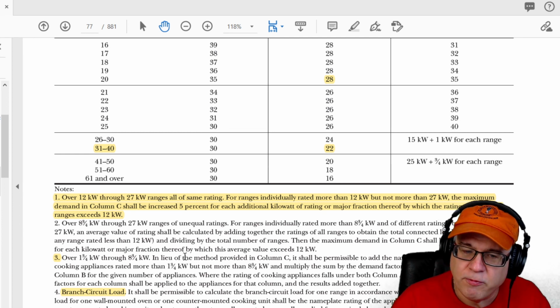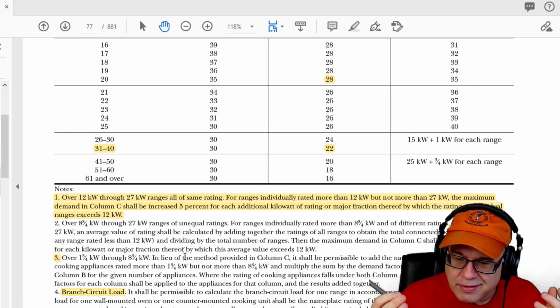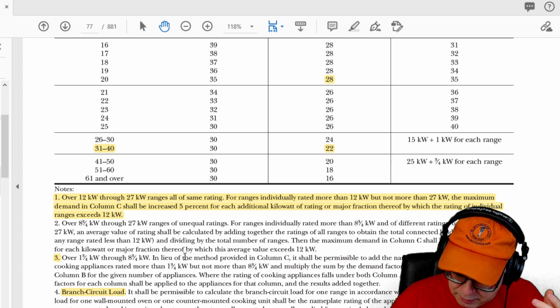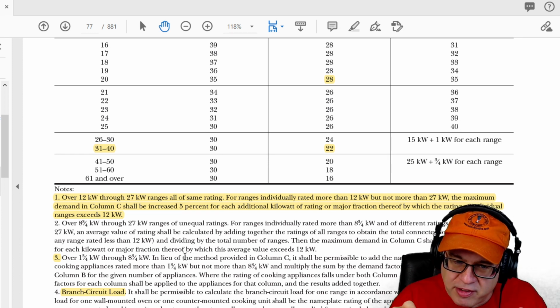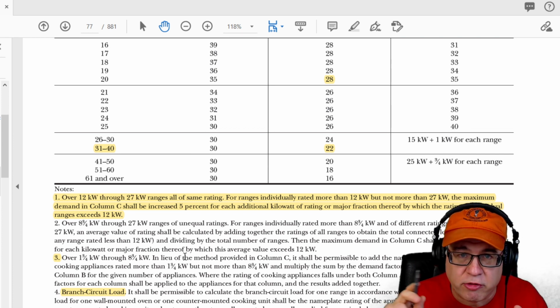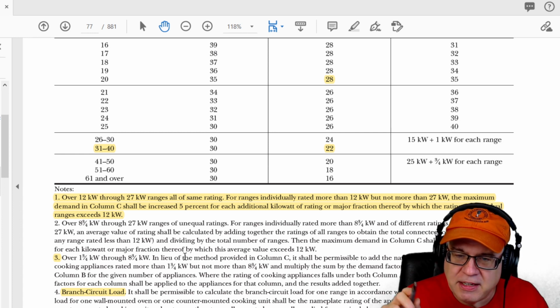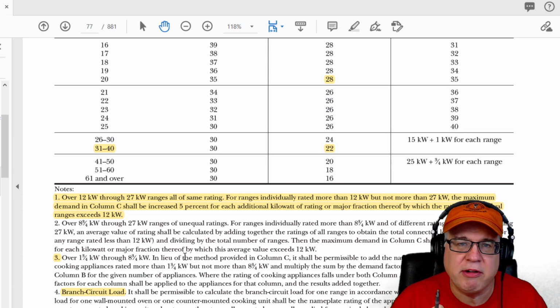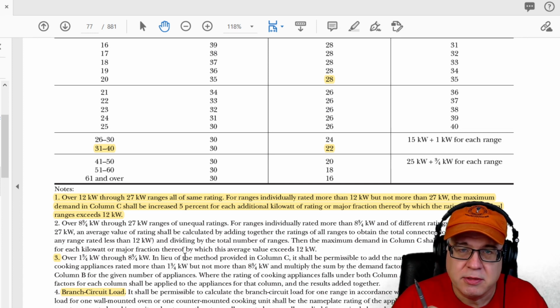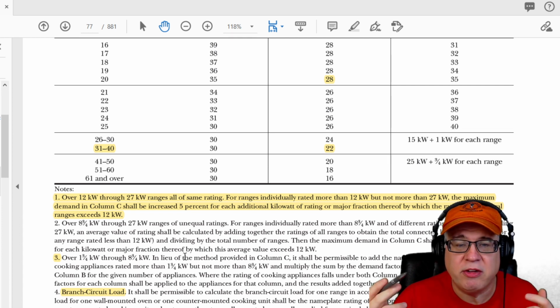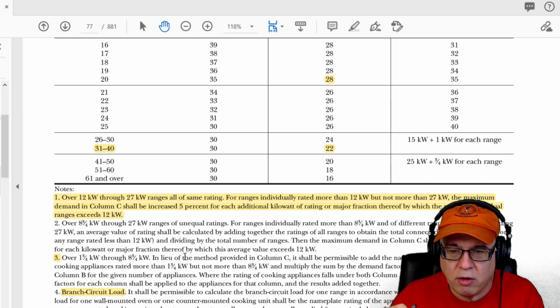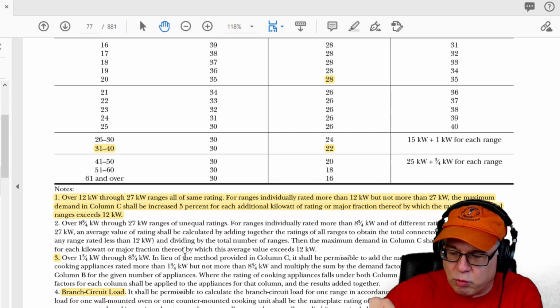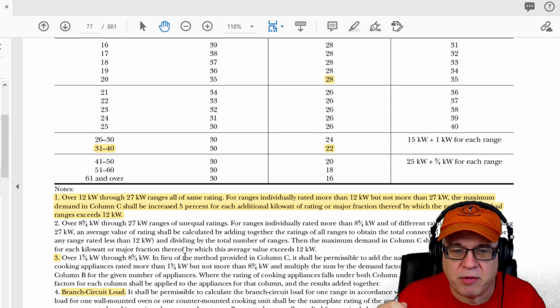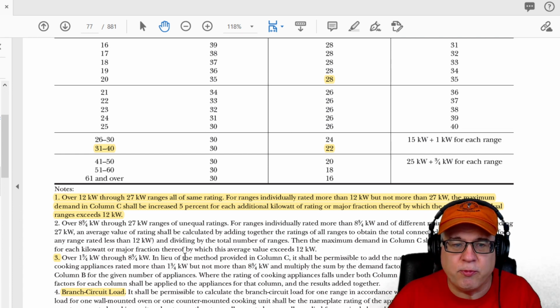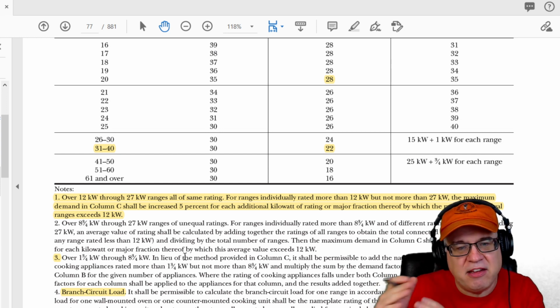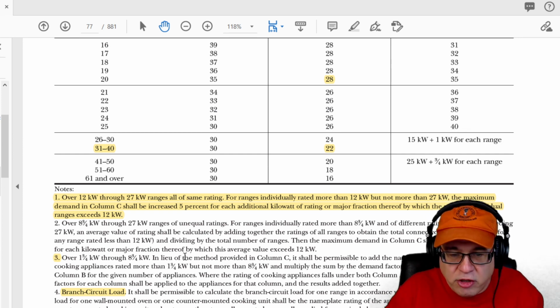So if you look at it this way, it makes all the sense in the world, guys, doesn't it? The demand in column C for one range is 8. But I'm only going to add 5% for every kW or major fraction. And again, 0.5 and greater is a major fraction. For every one that exceeds 12, I'm going to increase it by 5%. And what am I increasing 5% by? 5% of the 8 kW. So the easiest way to do that is, again, to get your number. I always just go 5 times how many? So again, it was 12, 13, 14, 15, 16, 17, 18, 19, 20, 21. That's 9 times 5 is 45%. I know that if 100 is the 8, to add the additional 45, I just multiply it by 145%. That gives me the additional 45%. And you do it from the 8.